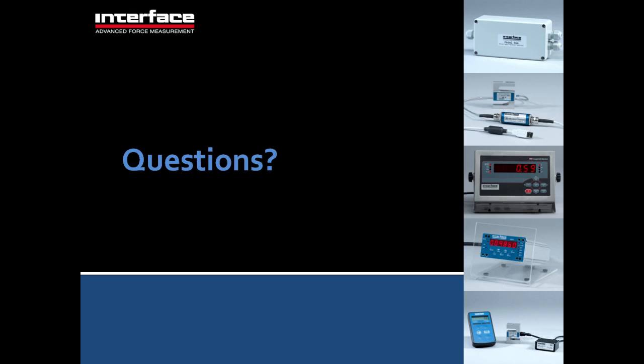How do you know what filter level to use? Well, that's another good question. It's a question we sometimes do ask the customer. In some cases, they don't really know the answer, and it's hard to say until you get the system installed. And so one easy answer to that is to try and choose an instrument that either has selectable filtering, and then you can fine-tune it in the field, or you choose one that has a fairly low amount of filtering, so a higher bandwidth, such as, say, 1,000 hertz.